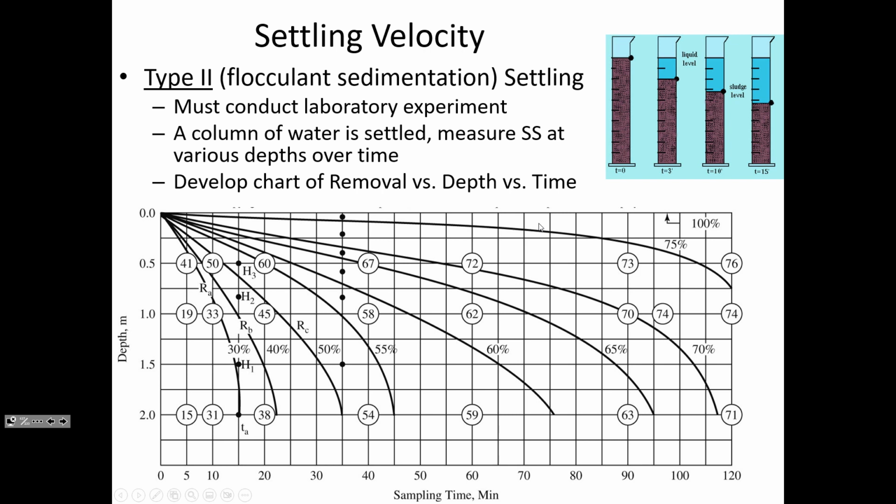And then you'd find out how big the settling basin needs to be based on this testing, and then you'd double it. They put in really generous safety factors because the consequence of not having effective removal of these particles is that it can affect human health. And so there's just enough variability in the conditions that affect settling that they generally would provide a pretty healthy factor of safety.